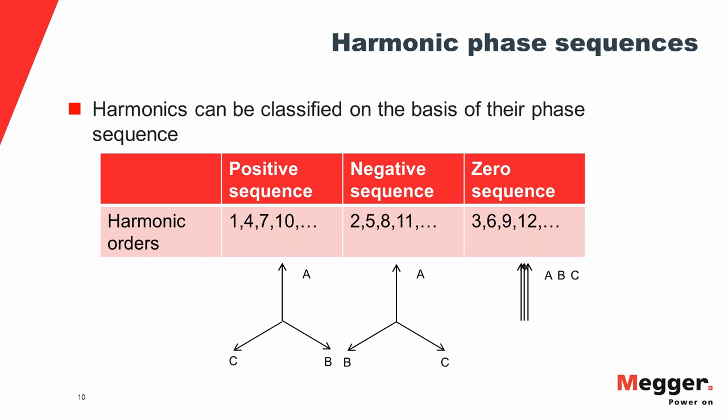Harmonics can also be classified by their phase sequence, which refers to the phase relationship between the three phases in a three-phase system. In a positive sequence system, B lags A by 120 degrees and C lags B by 120 degrees — moving clockwise on the vector diagram from A to B to C. In a negative sequence system, B leads A by 120 degrees and C leads B — moving counterclockwise. In a zero sequence system, there is no phase difference; all three phases are in phase with each other.